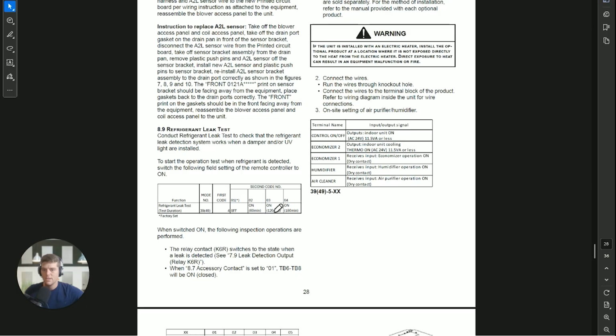You're going to find this is something that's going to be required in certain applications where inspectors want to see, hey, I know you have it wired up to open an outside air damper, to send off a siren, to report back to an alarm panel. Does it actually do that? Here's the test that you're going to do here in the system to make it happen right there. And yeah, that's most of it.